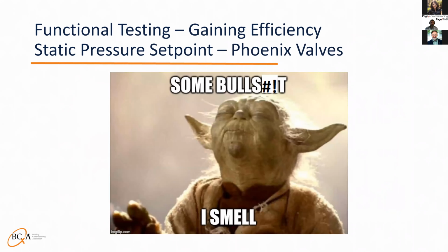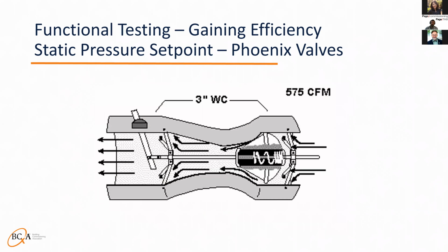Setting the static pressure set point with a Phoenix valve or similar. If test and balance says they cannot set static pressure set point on an AHU that serves lab valves, you can call BS. Every Phoenix valve, whether serving the supply or exhaust, will come with differential pressure ports to verify the valve is within its pressure range to control flow.